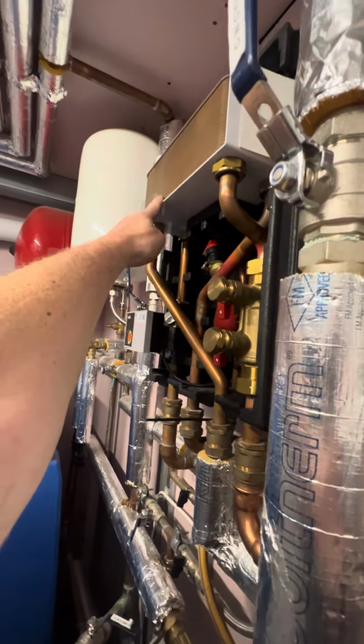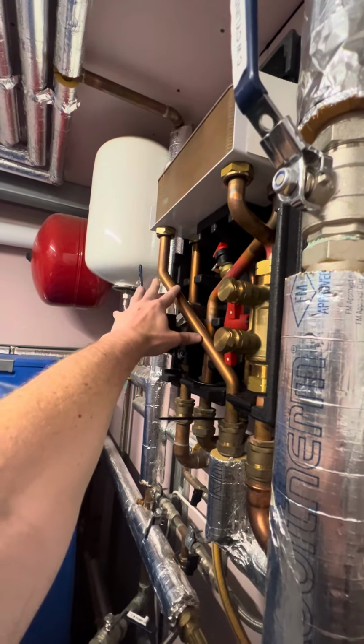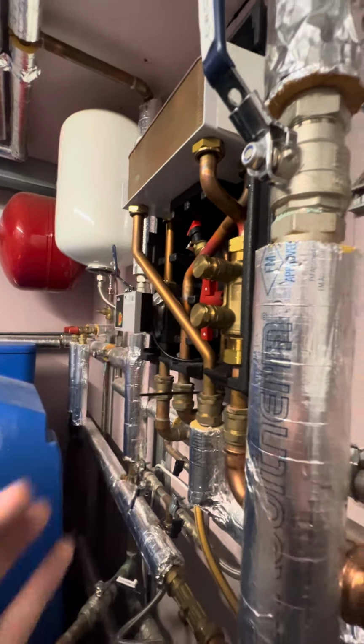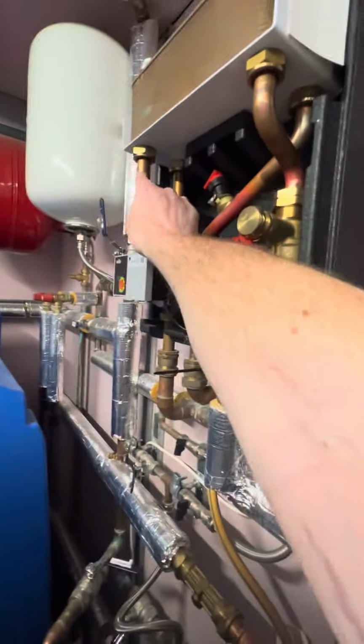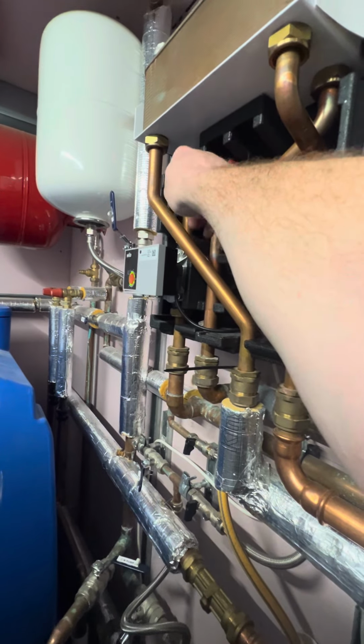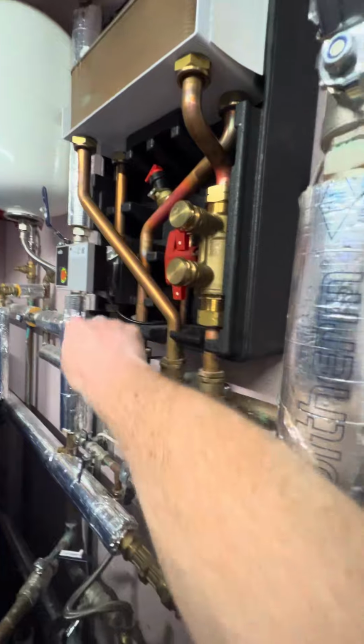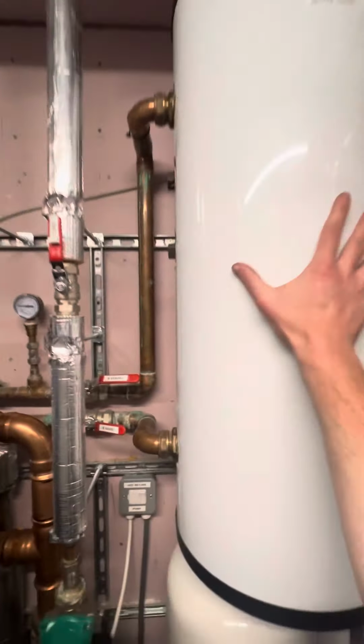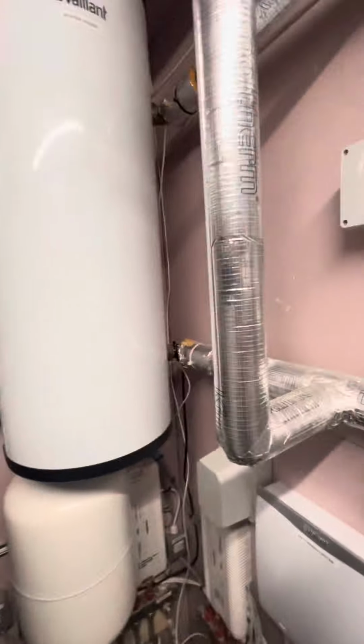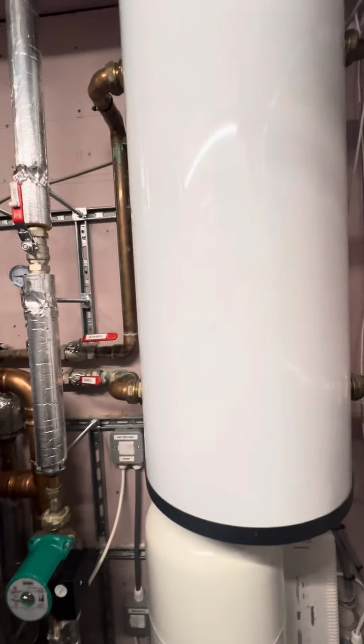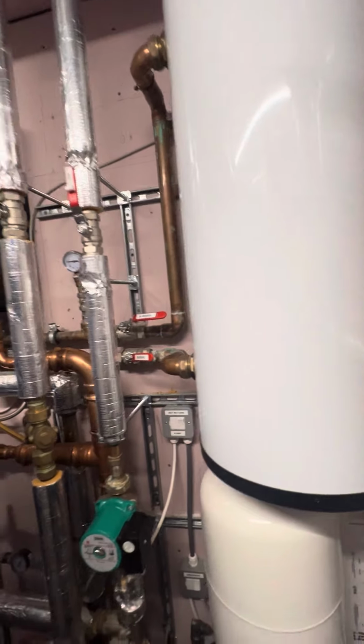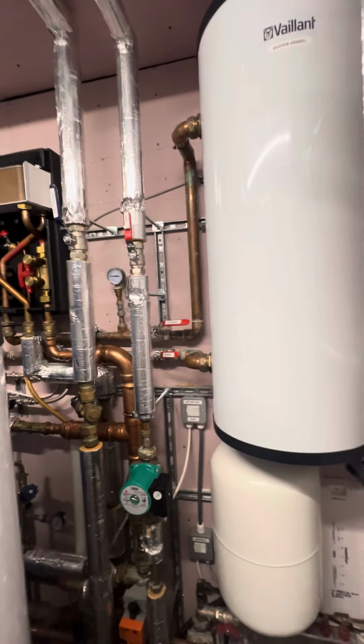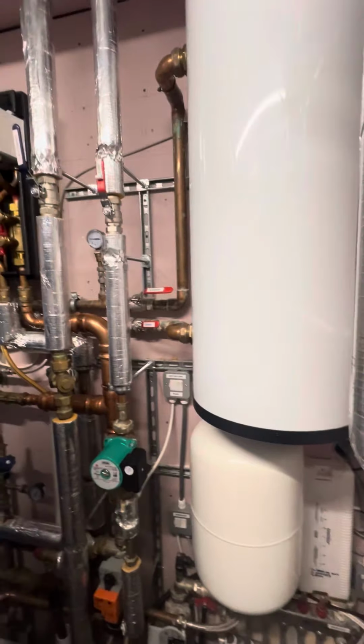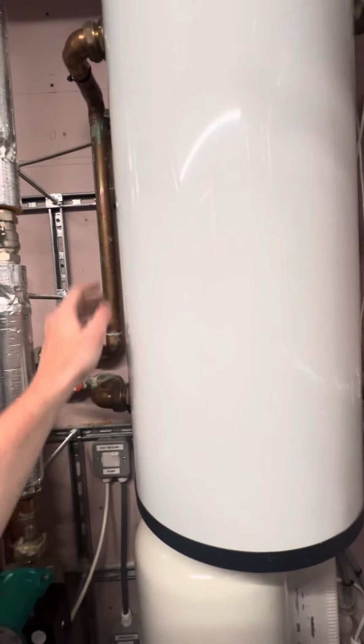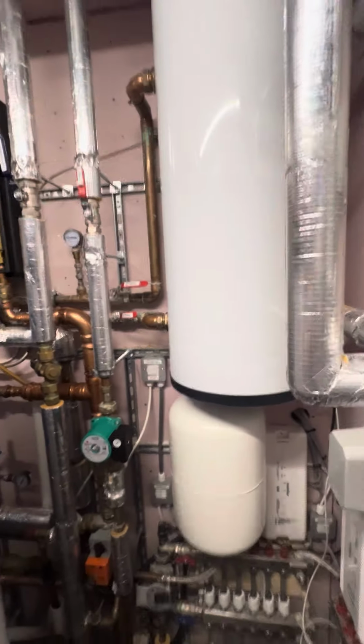Now, the secondary side of this here, so how we get from the heat exchanger to the underfloor heating and towel rails, is where it gets complicated and where we start to have some potential big efficiency losses here. So what we've got here, we've got another pump that just goes up into the plate heat exchanger and down across here to a 4-pipe buffer vessel here. Now, maybe the buffer vessel was required if the pipework's not large enough to be able to pump straight through off the built-in circulator pumps, or maybe they needed an additional volume in the system. But the way this works as a 4-pipe buffer is it provides hydraulic separation, but you also have quite a lot of mixing in here.